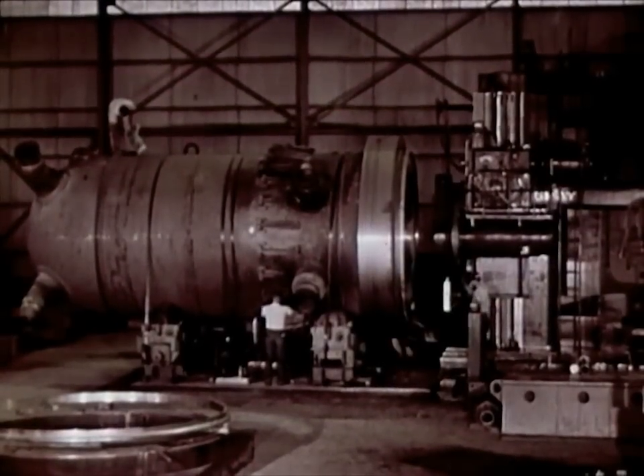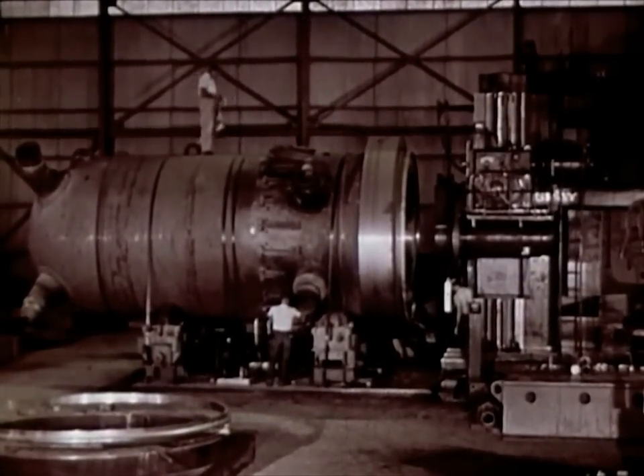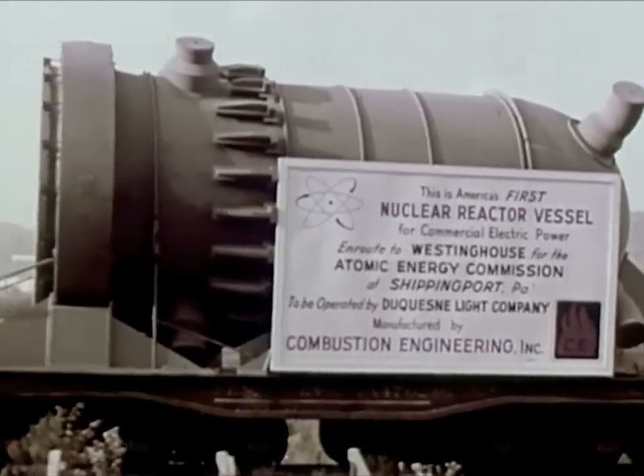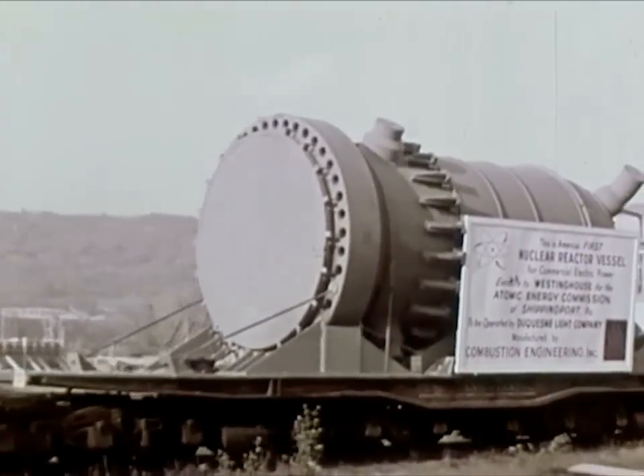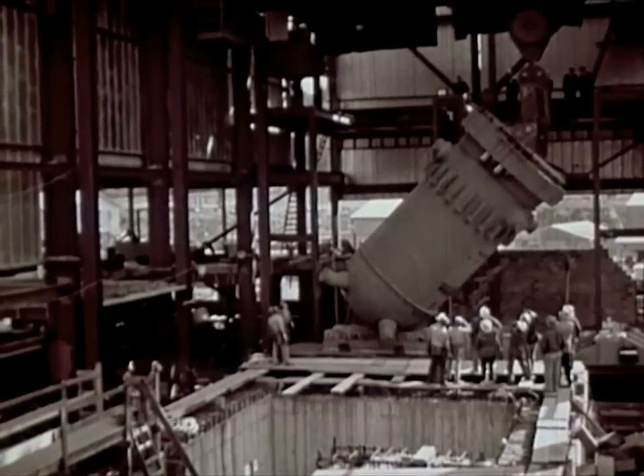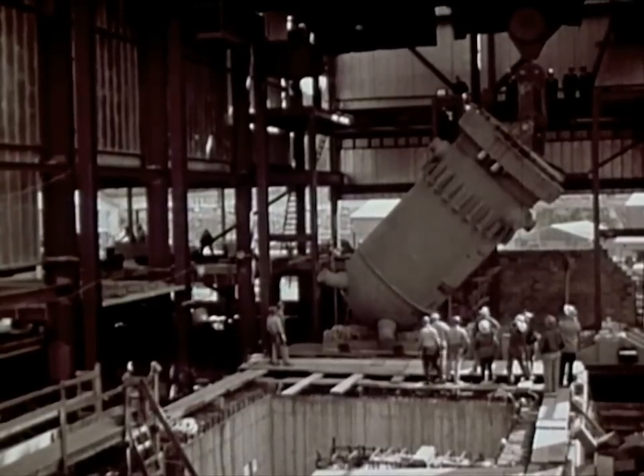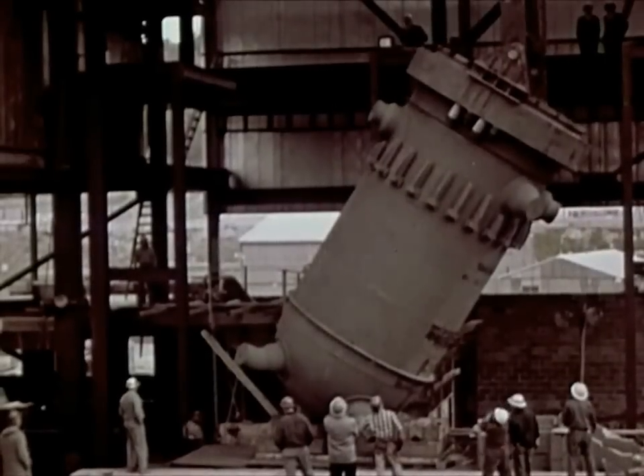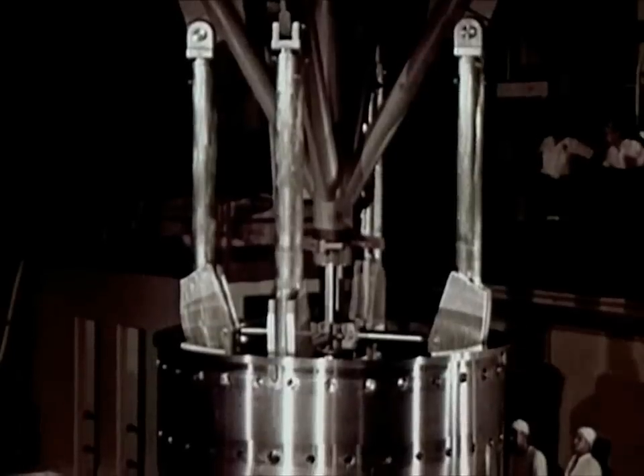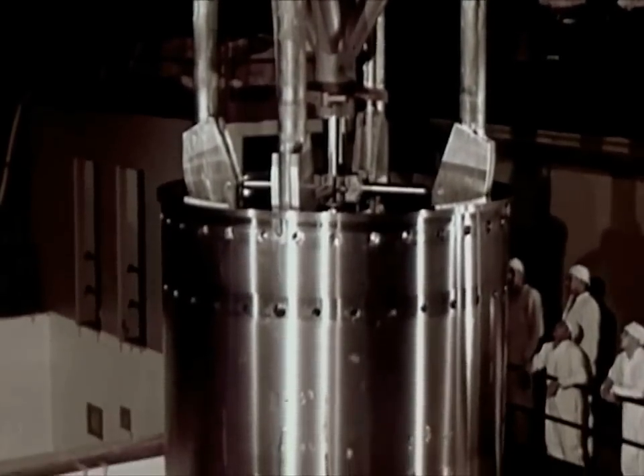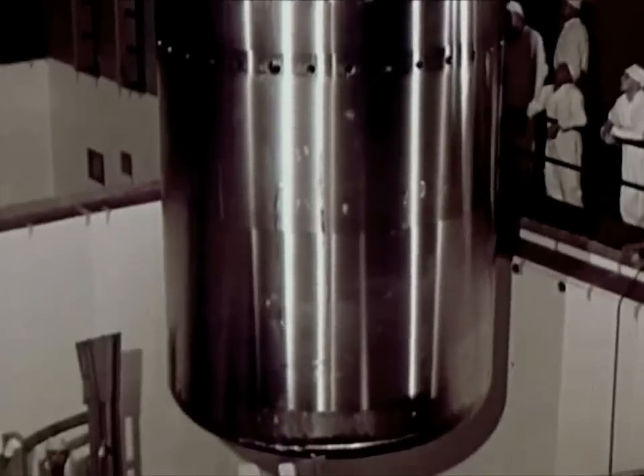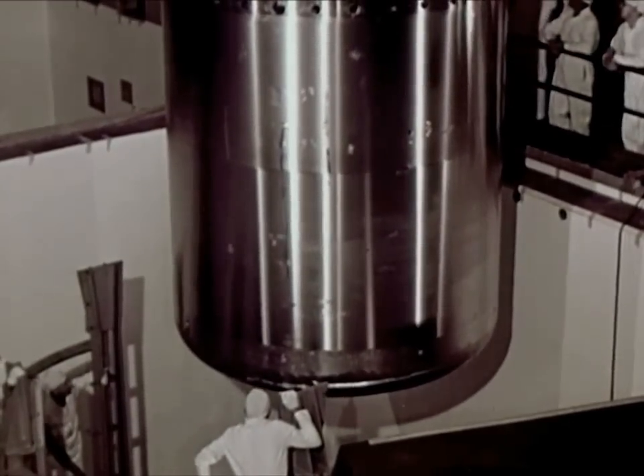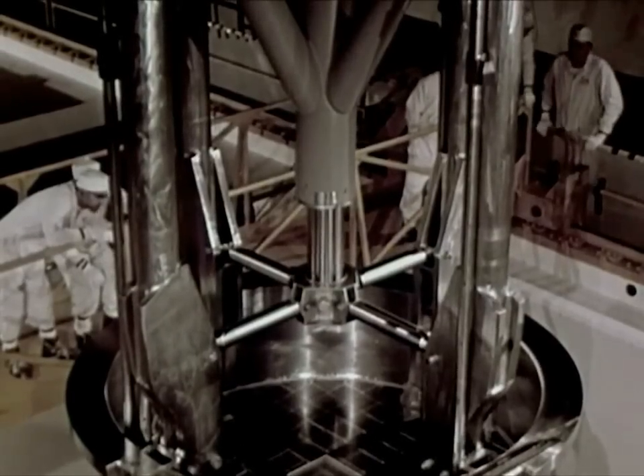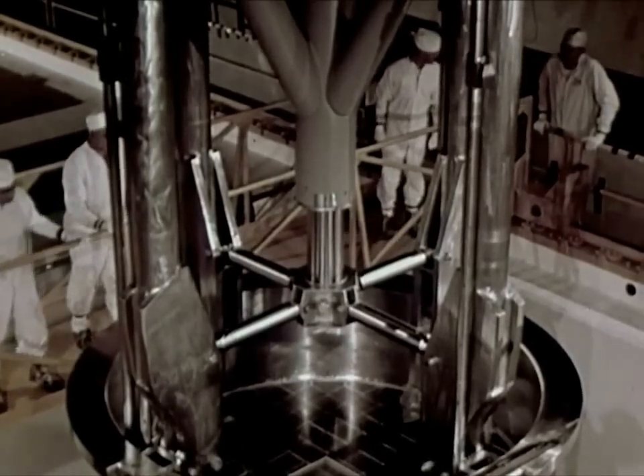With the reactor sphere in position, major equipment items began to arrive on the site. The 150-ton pressure vessel, having completed all of the shop processes involved in its fabrication, began its journey to Shippingport. It was installed on October 10, 1956. The basic methods employed for installing the units were similar to those followed in major construction projects. A high order of cleanliness was necessary while the primary system was open, such as during installation of the thermal shield. The climax of these operations came on October 6, 1957, the precise placement of the fuel core in the reactor.